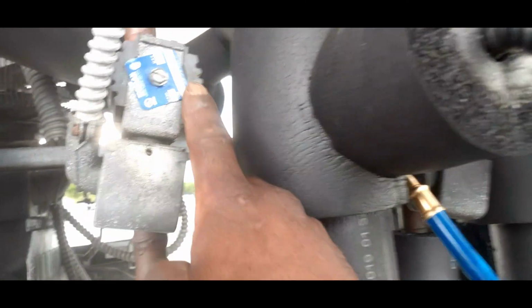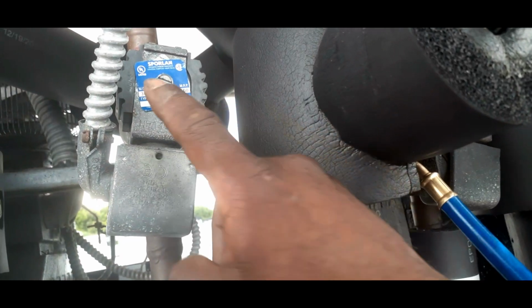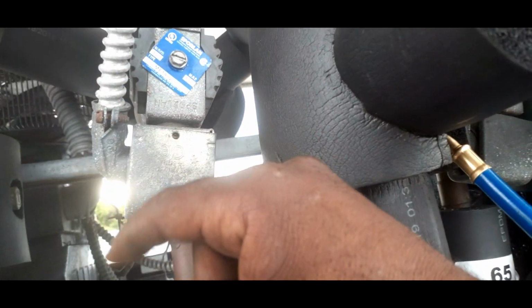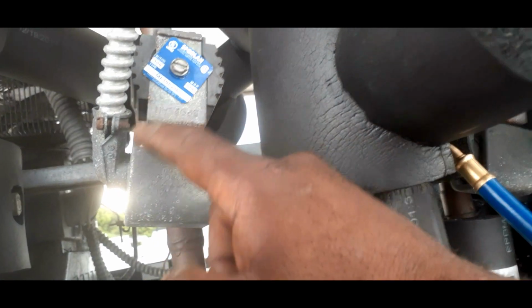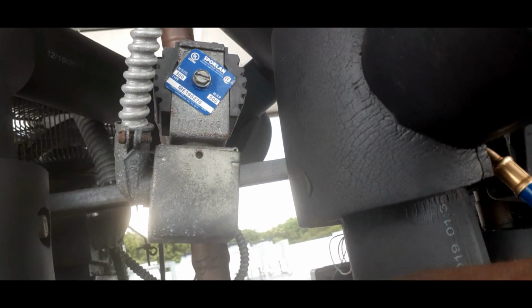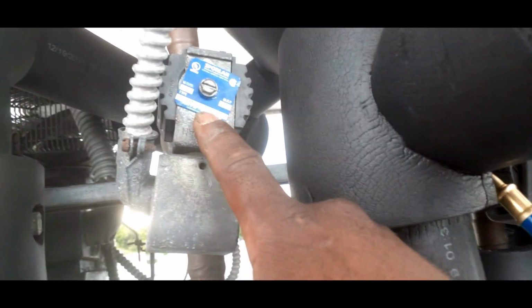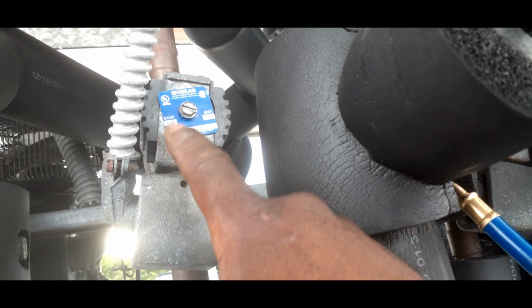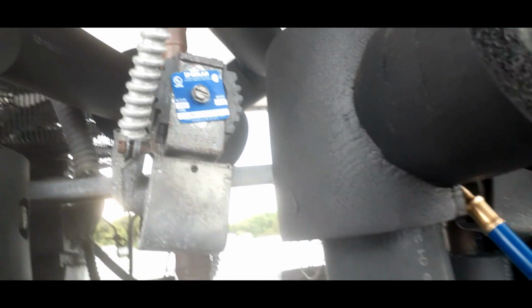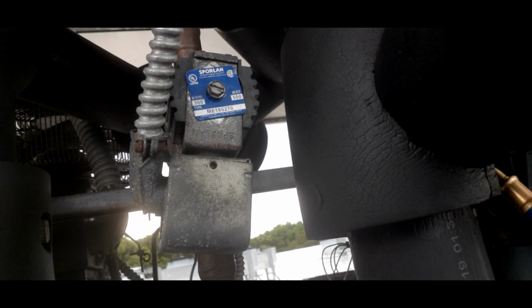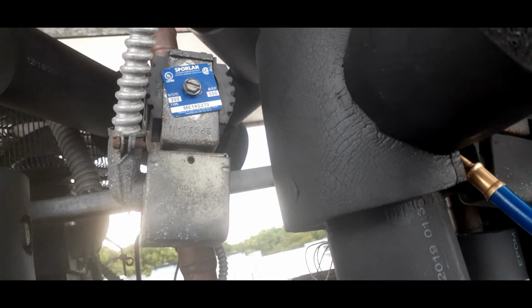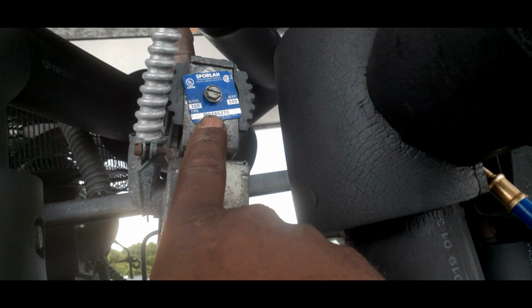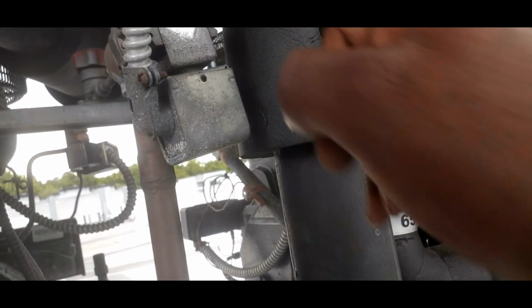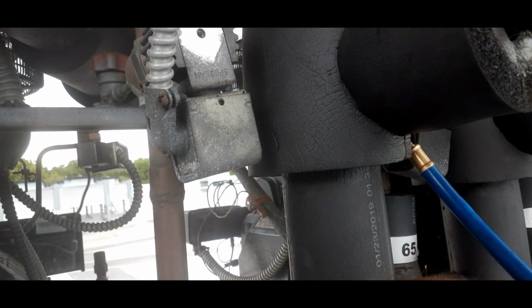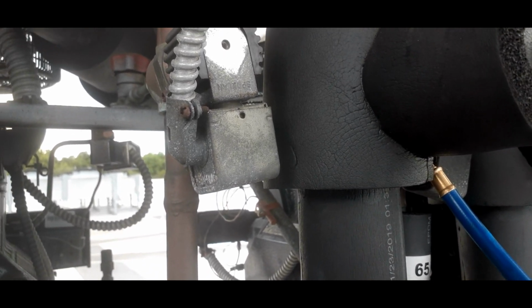Alright, so before I go any farther, this here is like a data sheet, identification, basically letting you know what size this is. So if you need to go get a rebuild kit, you want to look at these numbers right here. Head over to your local supply house, and give them these numbers, and you need to know if it's reverse acting or if it's normal. So just always take this information, never lose this. If you can, put the screw back on, this means a lot. When you get this off, you want to put a screwdriver in there, something metal, something steel. If you don't, it will burn up.